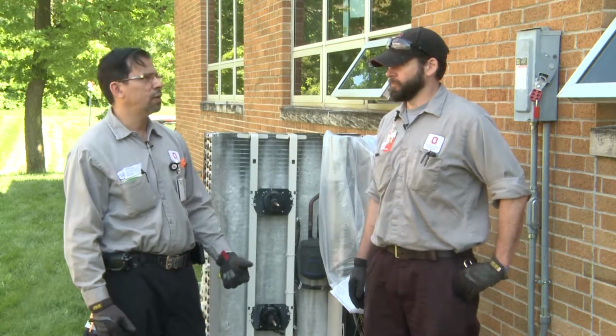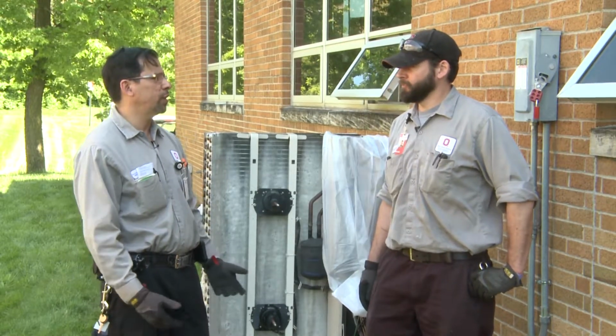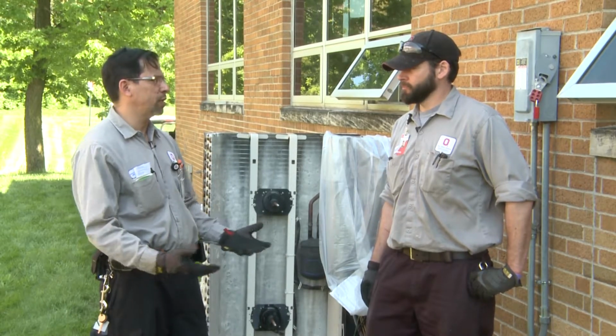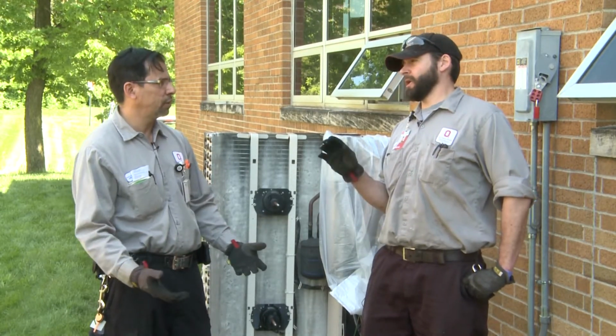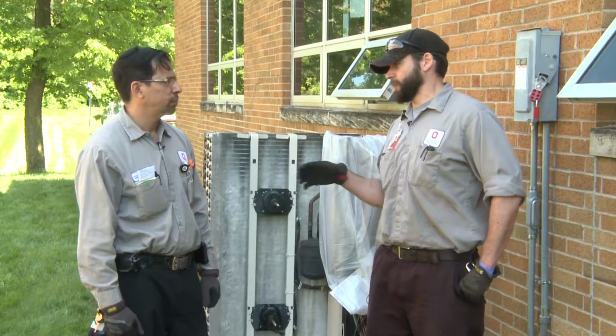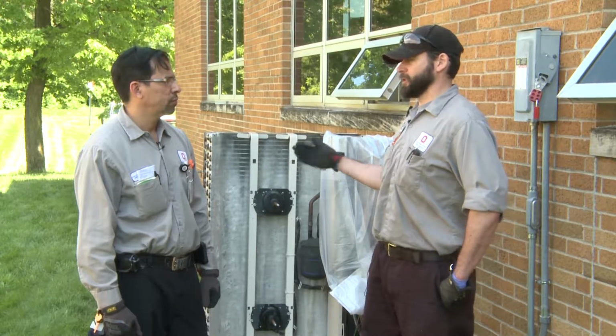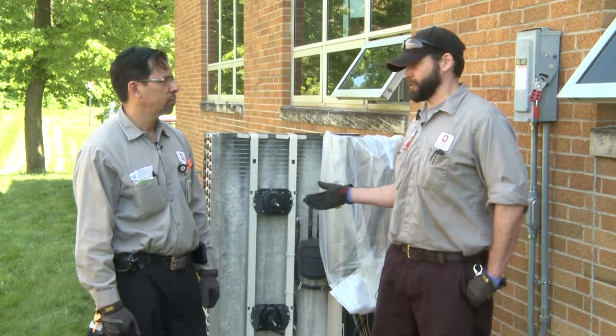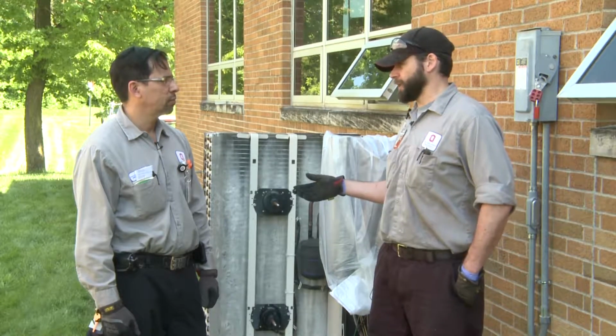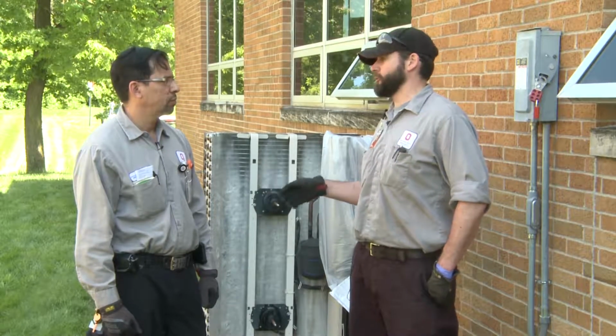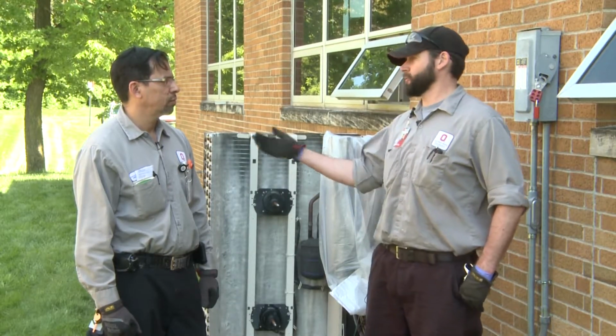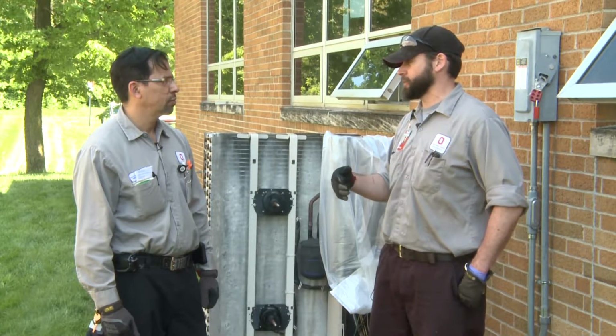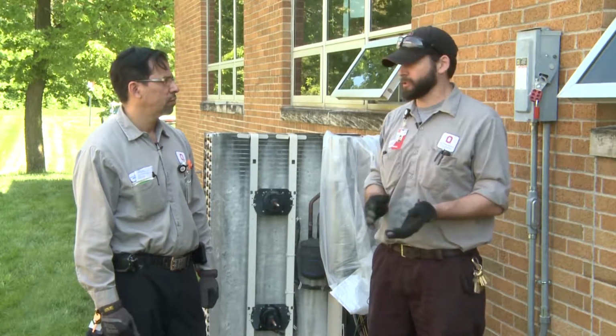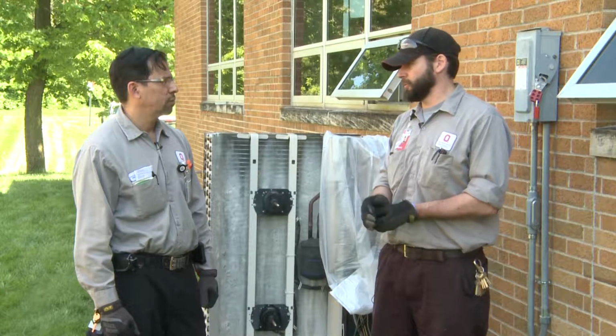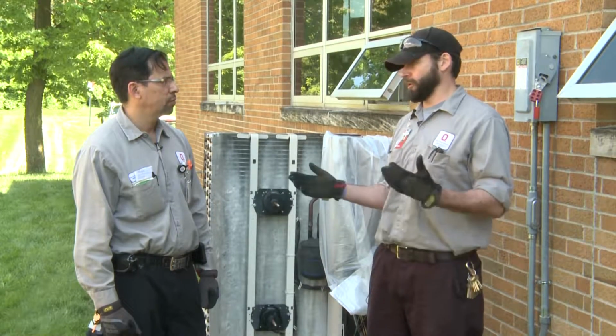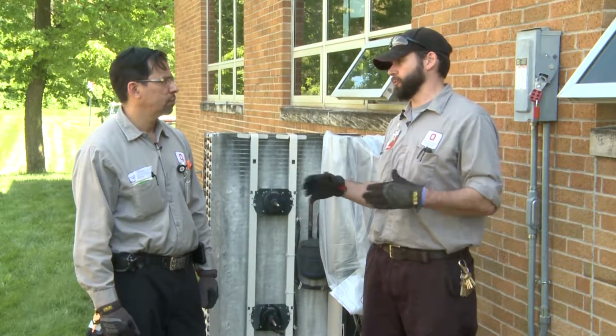Do you think a rainy day would be better to clean the coil since it's already raining? A light mist you might get away with, but a heavy rainy day you wouldn't want to do it, because you need to leave the coil cleaner on the coil long enough to clean it. Also on a windy day, which would typically also come with heavy rain, you don't want to be spraying this cleaner because the wind could spray it back into your face. It's not a big deal to get a little cleaner on your hands, as long as you rinse it off with water well, but you don't want to be working in a situation where you can't control the application.